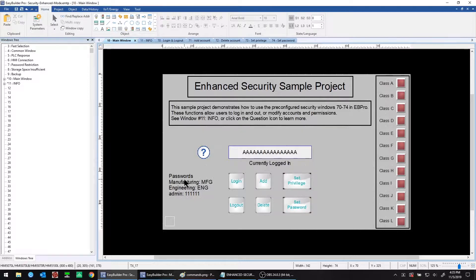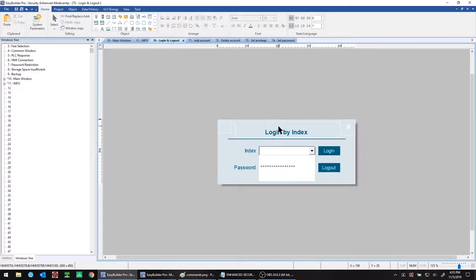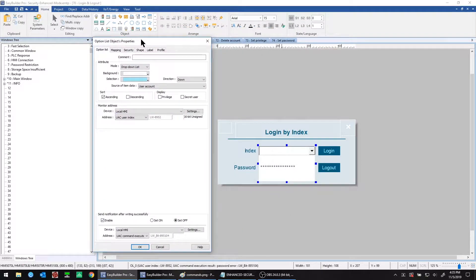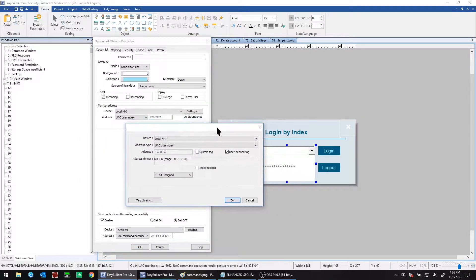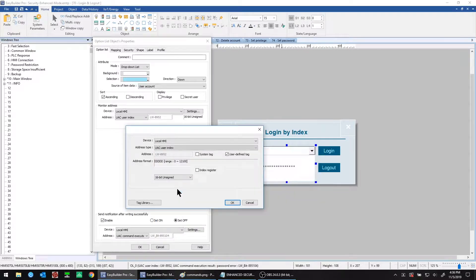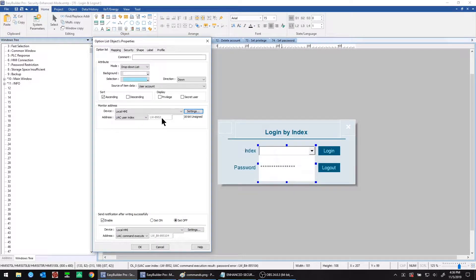Back to the main window, we also have text for the account setup in this example. To log in, we need a login window — we're taken to window number 70 where we can log in by user index. To allow operators to log in, you need to set up an option list object. From the object tab, select option list, choose drop-down list mode, and set the source of item data to user account. Set the monitor address to UAC user index — click on user defined tag to find this quickly. This is where the user selection will be stored.